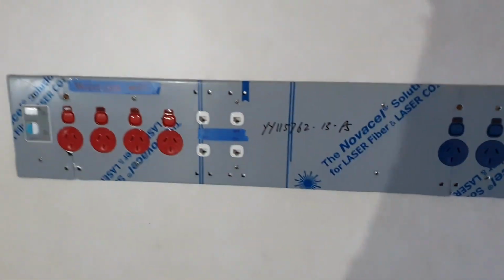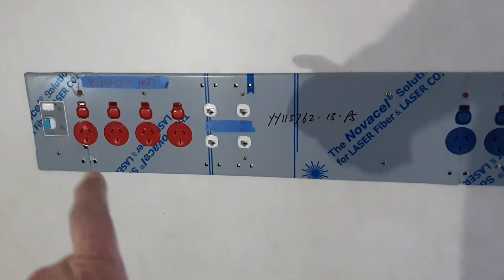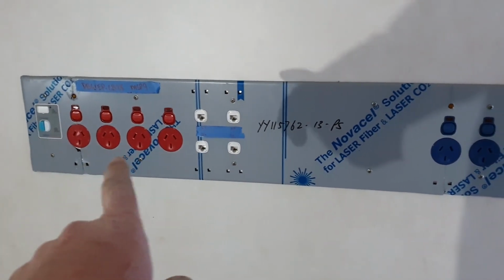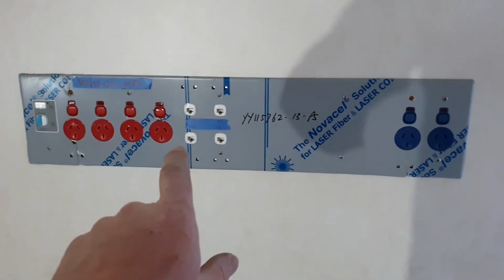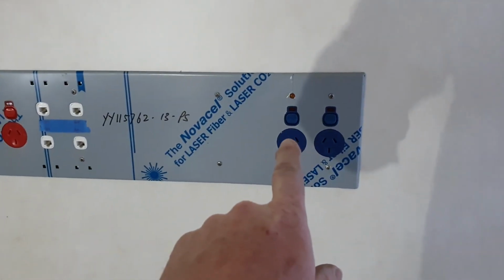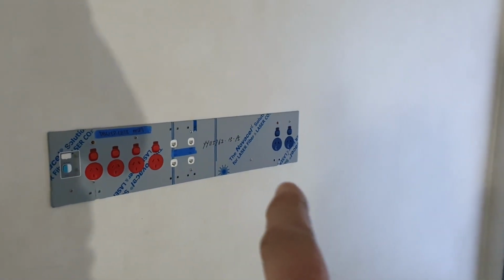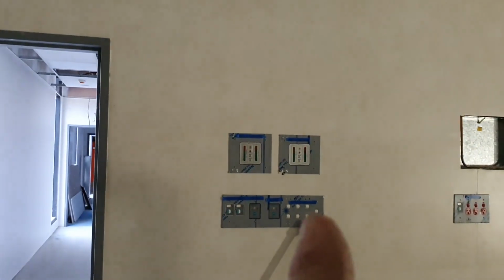Seven off, yeah. And then this is the last, or second last panel, which is just some RCD protected data outlets, some data points, and two UPS outlets. Those outlets aren't RCD protected, they're protected by an isolation transformer, those two.